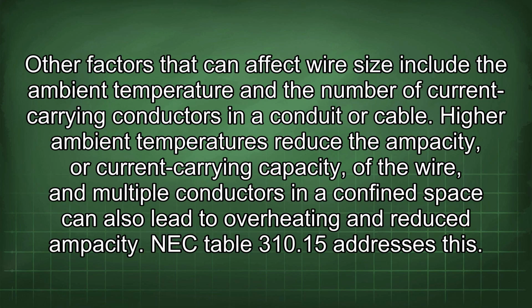Other factors that can affect wire size include the ambient temperature and the number of current carrying conductors in a conduit or cable. Higher ambient temperatures reduce the ampacity, or current carrying capacity, of the wire, and multiple conductors in a confined space can also lead to overheating and reduced ampacity. NEC Table 310.15 addresses this.